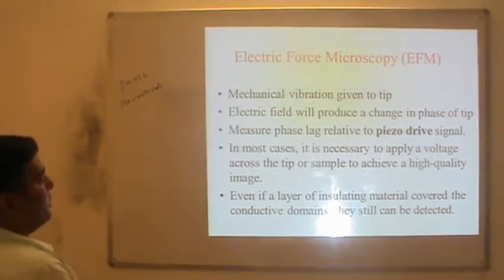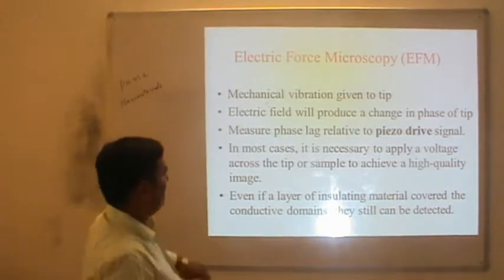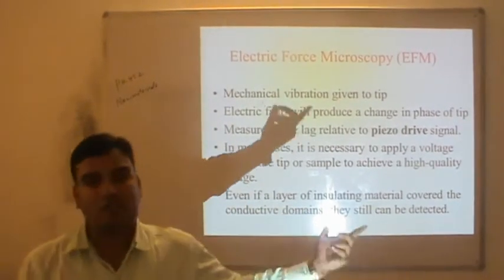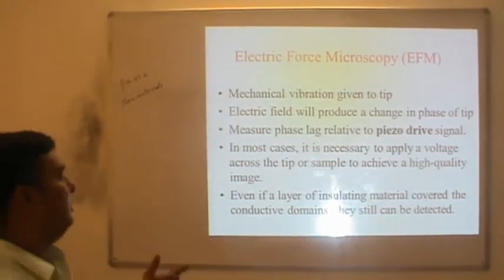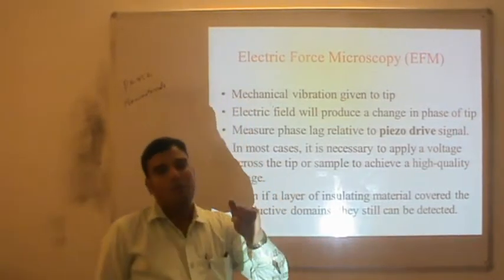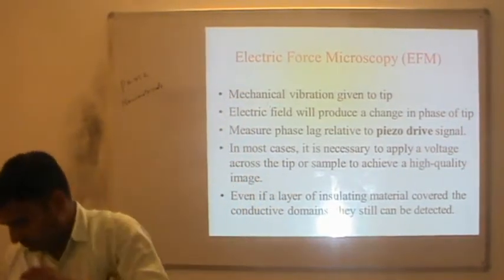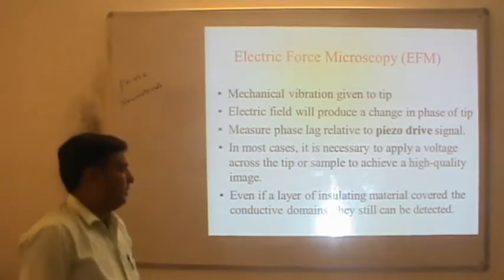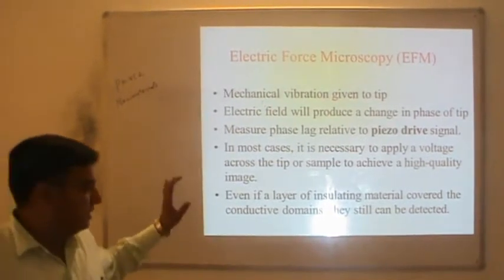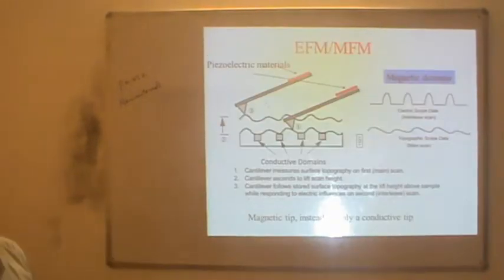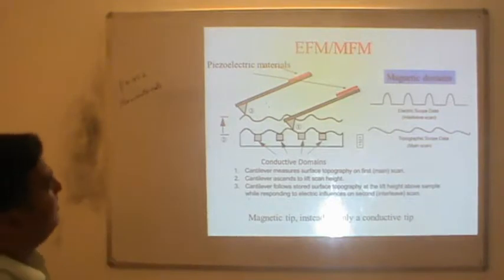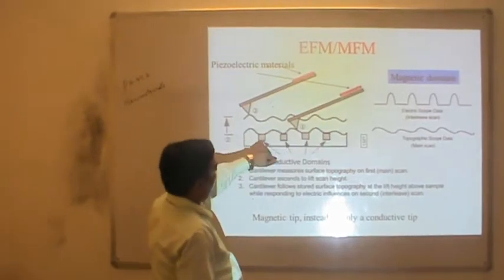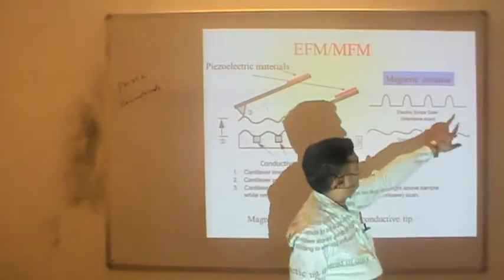In most cases it is necessary to apply a voltage across the tip and sample to achieve a high-quality image, because the voltage evident within the sample range is very small. The external applied voltage is important to get the best quality image. Even if a layer of insulating material covers the conducting domain, it can still be detected by electric force microscopy.